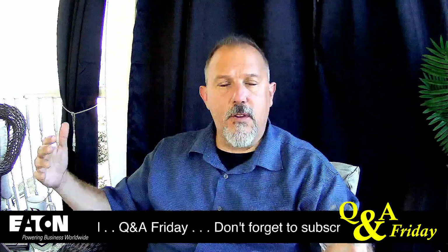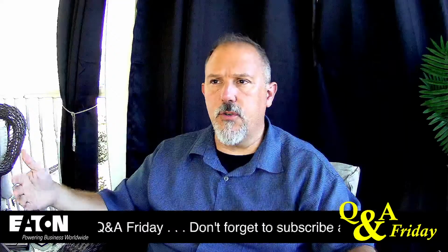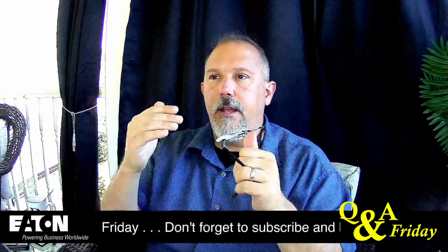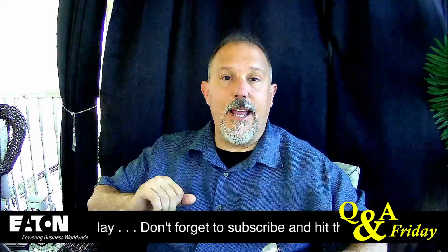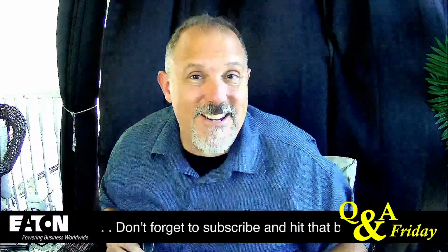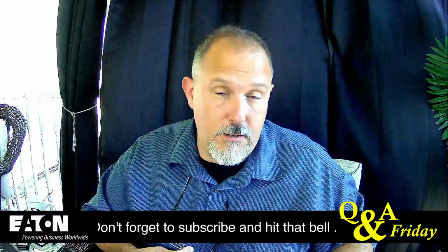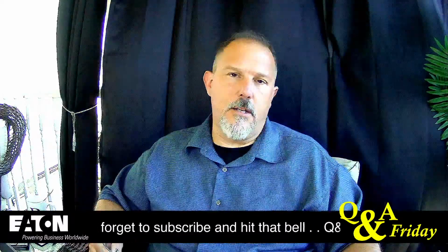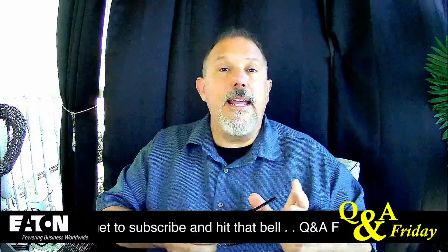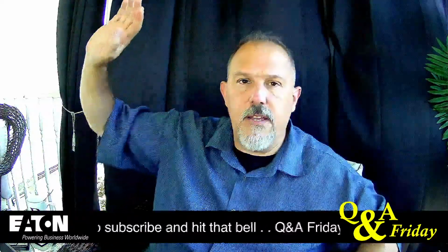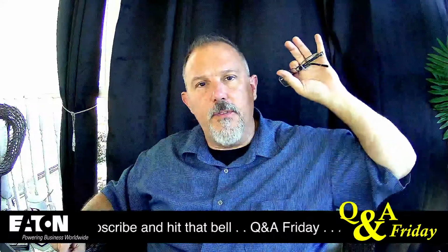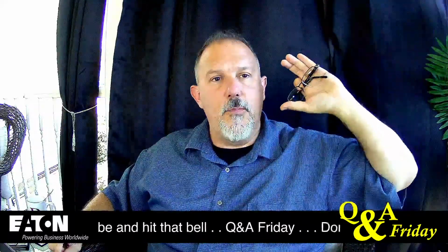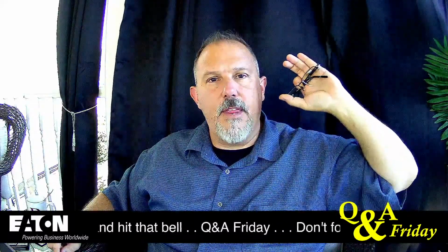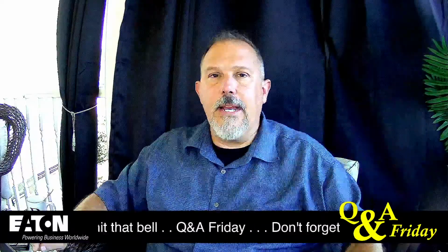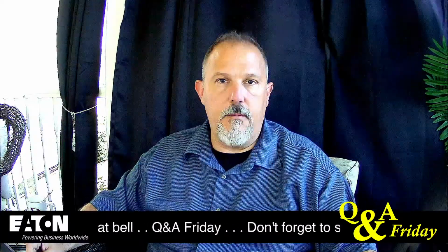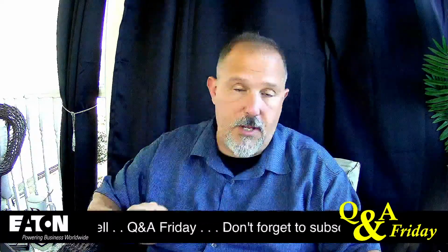And if I'm doing justified energized work in my motor control center, I could give you my engineering judgment, right? I could sit down and say, in my opinion, it's not going to propagate to the line side because there's a barrier over there. In my opinion, because you're working in the last cubicle and the main is up here on this top left-hand side cubicle, it's not going to propagate to that line side. That is just what it is, my opinion, or your opinion.